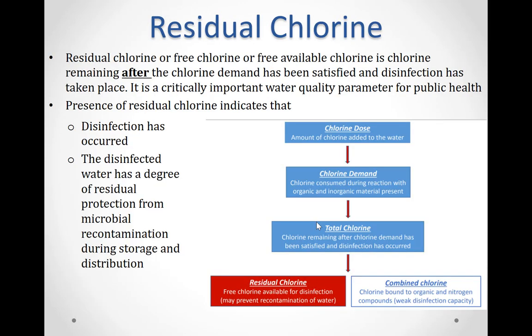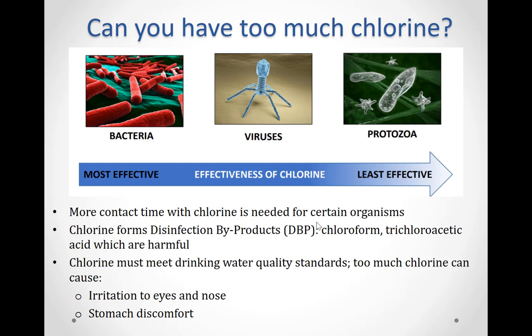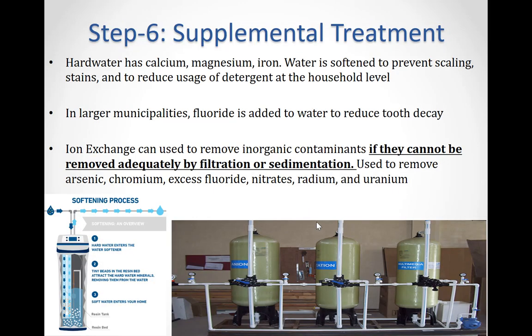Residual chlorine, or free available chlorine, is chlorine remaining after the chlorine demand has been satisfied and disinfection has taken place. It is a critically important water quality parameter for public health. Presence of residual chlorine indicates that disinfection has occurred and that the disinfected water has a degree of residual protection from microbial contamination during storage and distribution. However, chlorine also forms disinfection byproducts, or DBPs, such as chloroform and trichloroacetic acid, which are harmful. Thus, chlorine must also meet drinking water quality standards — too much chlorine can cause irritation to the eyes and nose as well as stomach discomfort.